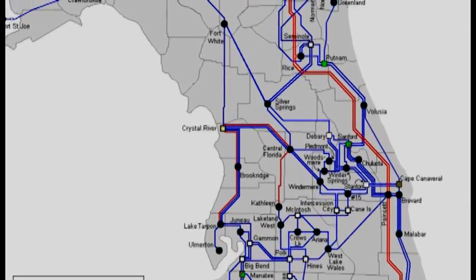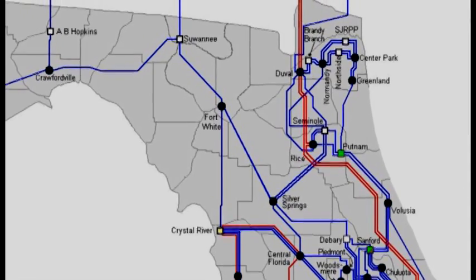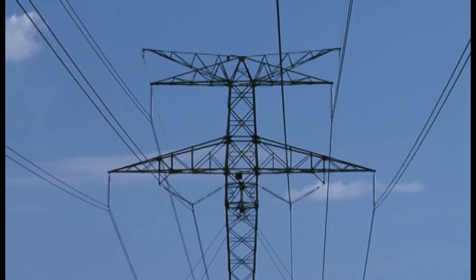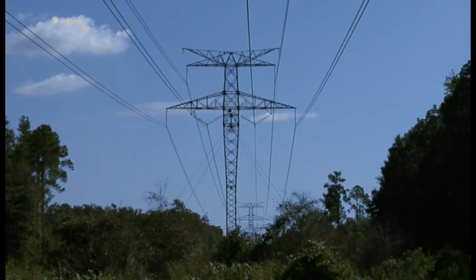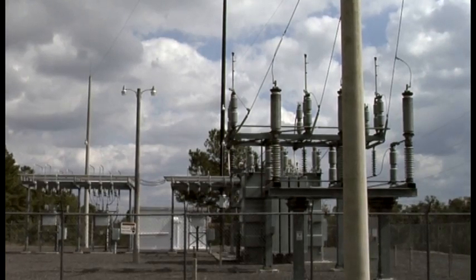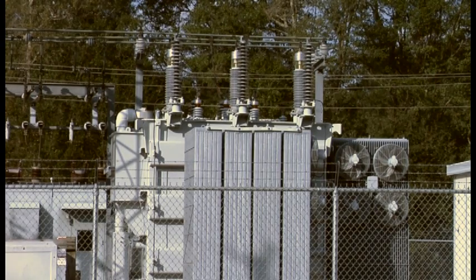The Florida transmission grid ensures that electric service can be quickly restored from another source if a power plant connected to the grid trips offline unexpectedly, and also allows some electric utilities connected to the grid to purchase power from other sources more economically than they can sometimes produce it. In Florida, transmission lines vary in size and carry power at levels ranging anywhere from 69,000 volts to 500,000 volts. Some transmission lines are routed through transmission substations, which are used to change the voltage level passing through the substation, either up or down. Other transmission lines deliver the power directly to distribution substations, which are strategically located throughout the service territory and are used to reduce the voltage being fed into them to a level appropriate for the area the substation is serving. Their placement in the system is based on customer density and the electric load requirements of the vicinity.